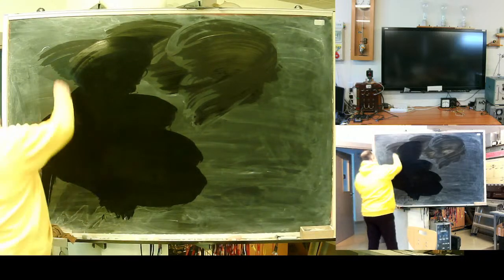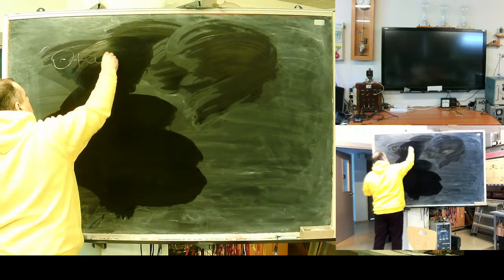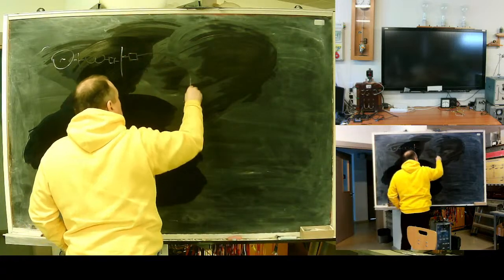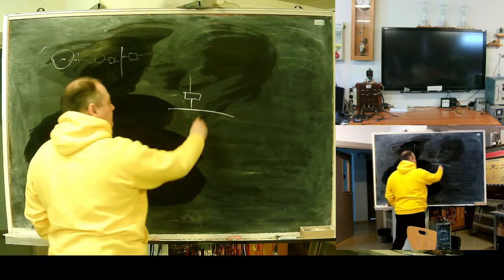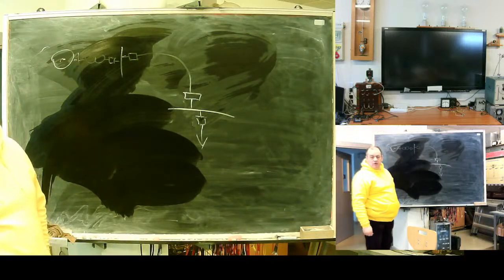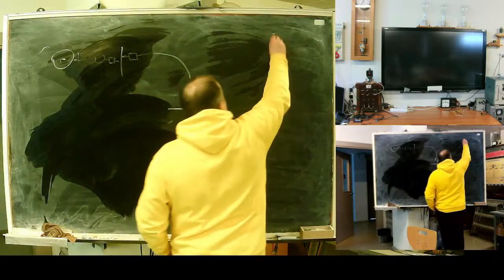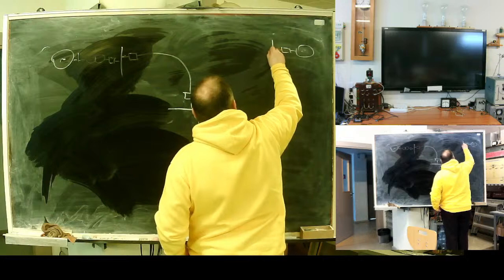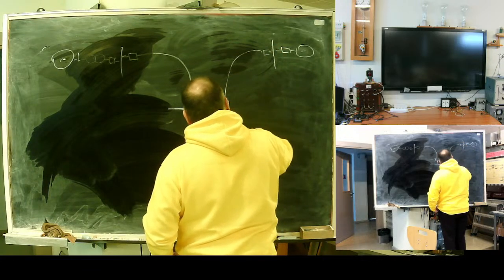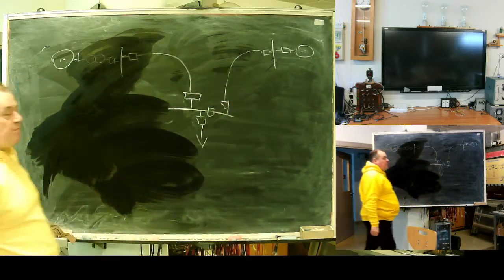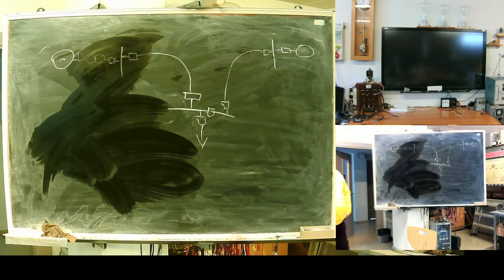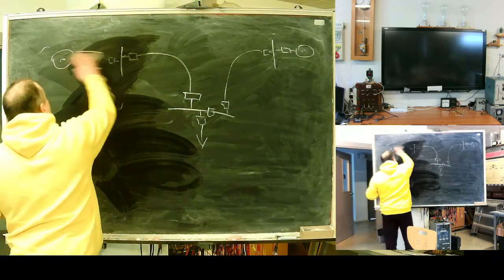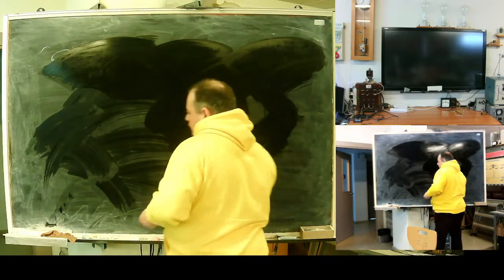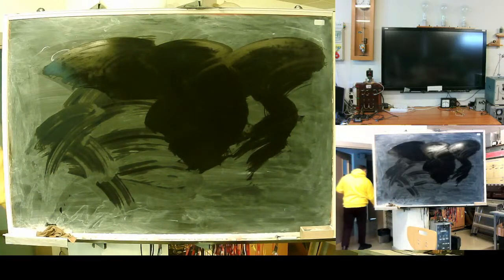Sometimes inter-substation. Problem, you have, let's say, substation 1, line, big customer. It's not enough. You cannot maintain this customer by one line. So you take power, maybe switch like this, you take power from another one. City networks, when you are obliged to maintain two sources for fire extinguishing system. Also, so let's try to understand what happens when a line is powered or energized from both ends.